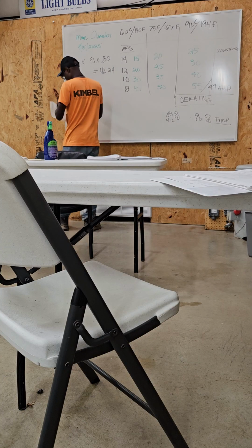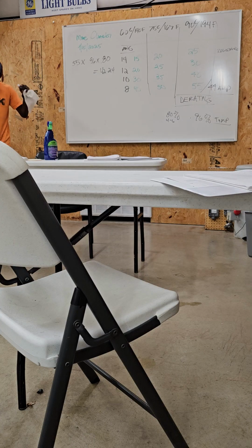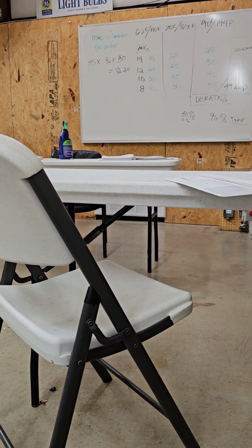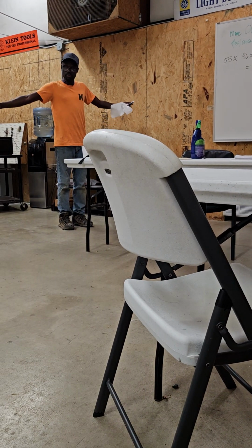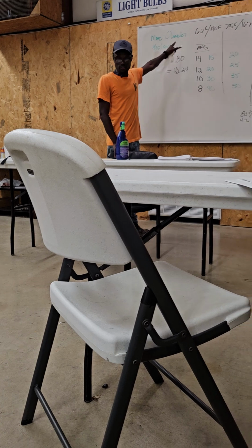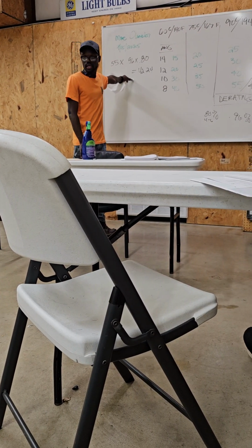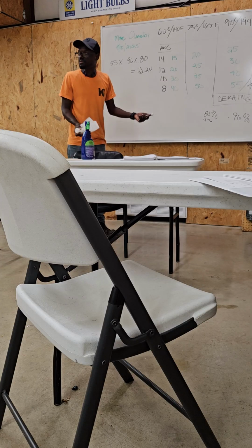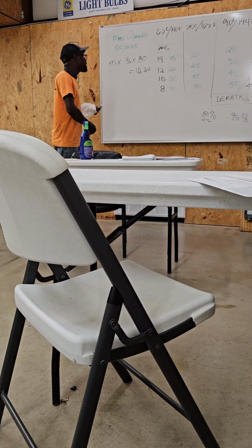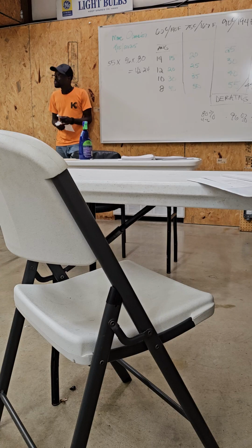So, now that is the only way this thing will work, if I'm going from there to there. Here's my panels over here, let's say I'm only going a couple of feet. But if I decided to put voltage drop on this, it will be dropped way down. This thing can probably only pull maybe 30 amp. But that's okay. The only reason why we're using number 8 is because we were thinking of voltage drop.